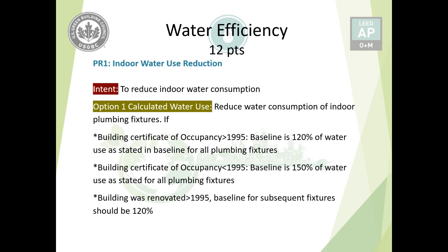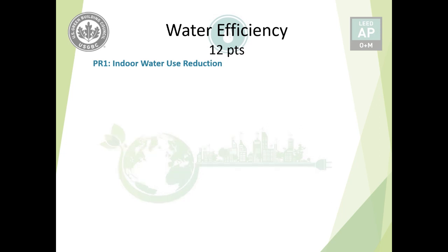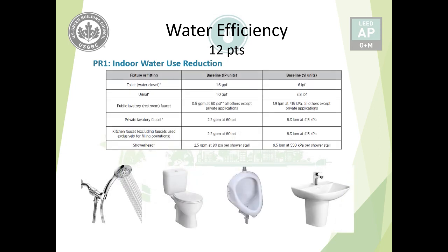The baseline fixtures should follow: 1.6 GPF for toilet, 1.0 GPF for urinal, 0.5 GPM for public lavatory, 2.2 GPM for private lavatory, 2.2 GPM for kitchen, and 2.5 GPM for showerhead. You have to add 20% or 50% based on the certificate of occupancy of your building. This table gives the flow rate of your sanitary fixtures.